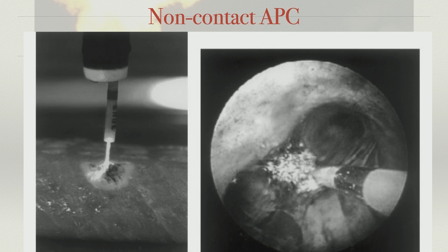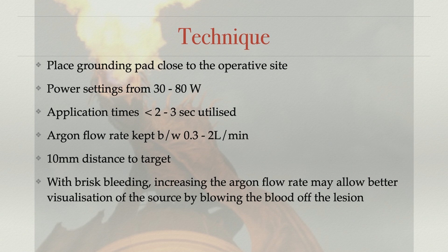So what is the technique? Basically you have a grounding pad because you want to create a circuit. The patient has a pad on his body. You can put it closest to the surface where you're working. The power settings are between 30 to 120 watts, but usually 50 is more or less sufficient. That is the setting that's on my APC machine. The application time, depending upon the mode, is about 2 to 3 seconds. The argon flow rate, which is automatically adjusted when you attach the cylinder, is between 0.3 to 2 liters. And 10 millimeters, like I've stressed multiple times, should be the distance to the target tissue.